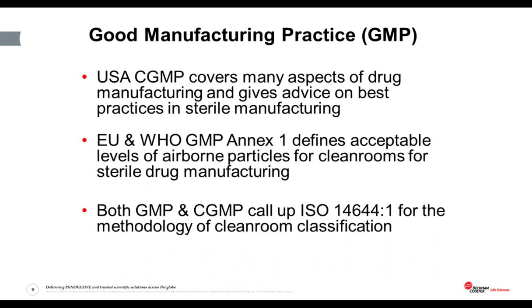The GMP rules and regulations in North America — the CGMP document — cover many aspects of drug manufacturing and give best advice on practices in sterile manufacturing. The European and World Health Organization share the same GMP Annex 1, which defines acceptable levels of airborne particulate contamination for clean rooms used in sterile drug manufacturing. Both the European and North American GMPs call up ISO standard ISO 14644-1 for the methodology of clean room classification.